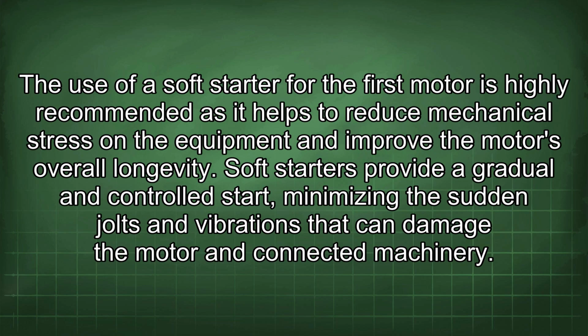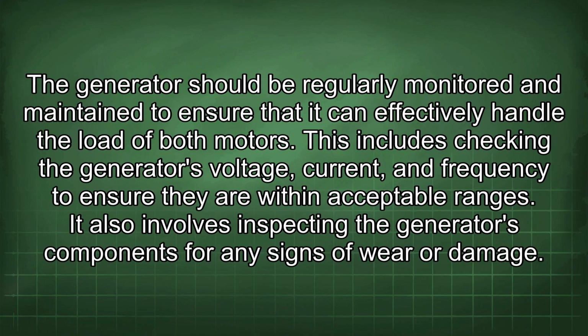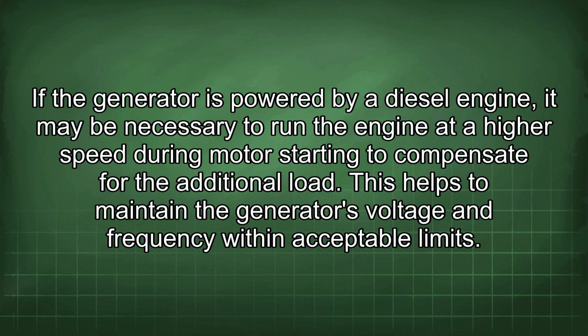The use of a soft starter for the first motor is highly recommended as it helps to reduce mechanical stress on the equipment and improve the motor's overall longevity. Soft starters provide a gradual and controlled start, minimizing the sudden jolts and vibrations that can damage the motor and connected machinery. The generator should be regularly monitored and maintained to ensure that it can effectively handle the load of both motors. This includes checking the generator's voltage, current, and frequency to ensure they are within acceptable ranges. It also involves inspecting the generator's components for any signs of wear or damage. If the generator is powered by a diesel engine, it may be necessary to run the engine at a higher speed during motor starting to compensate for the additional load.